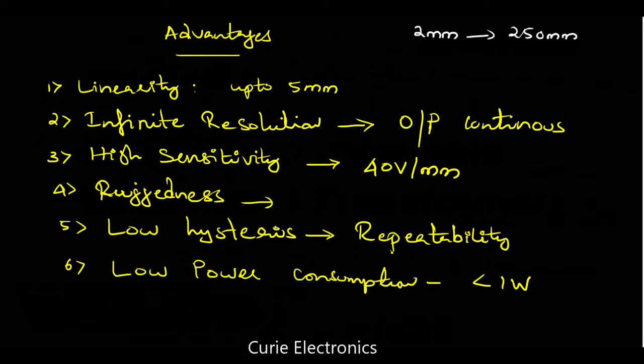Another advantage is ruggedness, meaning it is very sturdy and solid. Due to that, it is used in aerospace and military applications. Another advantage is the low hysteresis property of LVDT. Due to low hysteresis, the repeatability is good. Repeatability means, for 1 mm movement, this LVDT gives 40 volts. If you do the same experiment 1000 times or even 1 lakh times, you get the same reading, 1 mm movement, 40 volts, due to the low hysteresis property. And it consumes very little power, less than 1 watt. These are the advantages of LVDT.